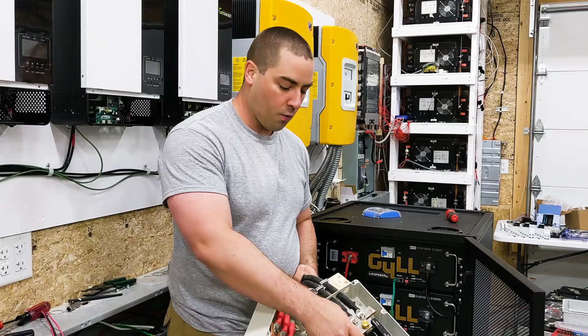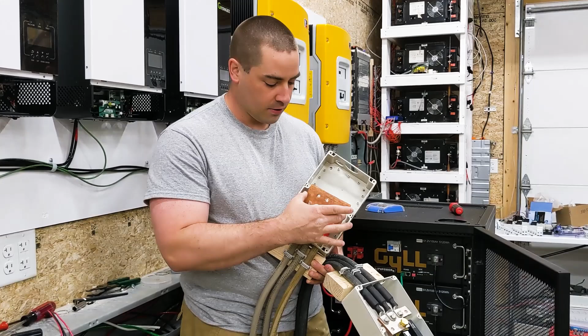I'll put this on top of the cabinet and use some pieces of 4/0 wire to go from the shunt down into the bus bar built into it. For the positive side, I wouldn't actually need this box with the bus bar — I could run these cables directly to the built-in bus bars. There are 4 spots in here where you could screw to them.